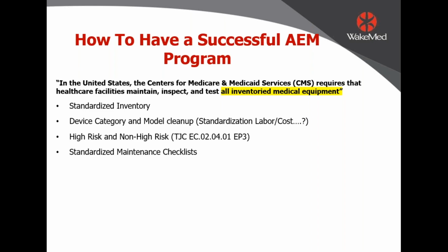So if there's an issue with it, you would put yes or no. So we have yes, no, we have pass, fail. We even have categories where you can put numbers in there. So if you're doing a centrifuge PM, you can put the RPMs that you have, and it has to be within a certain tolerance. So you have to have a standardized maintenance checklist that all your technicians can follow.